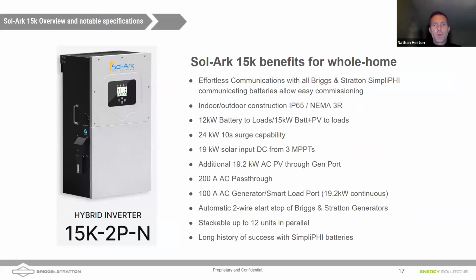So some features of the Sol-Ark 15K. It is capable of 12 kilowatts continuous from batteries alone. If you've got solar and batteries, it's capable of 15 kilowatts of sustained output. But if you've got air conditioning, etc., you can surge to 24 kilowatts for 10 seconds. So that's to start your compressors on large air conditioners, or a large well pump, something like that. So it does have that ability to surge up to 24 kilowatts. Bring in 19 kilowatts of DC coupled solar through 3 MPPTs.